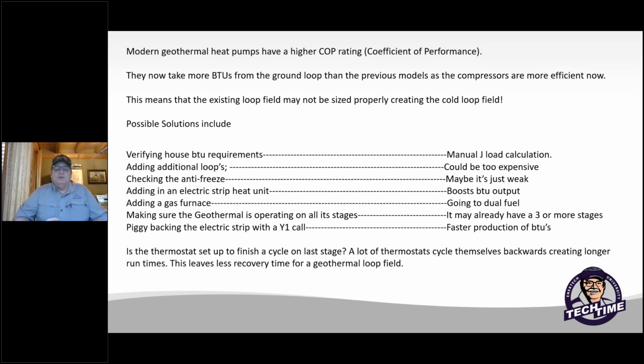I think that was a really important thing we saw this year where people didn't go and double check the internal programming of your thermostats. And I think that we had a couple occasions this year too where they had electric strip heat, but it took a long time for the third stage to come on.